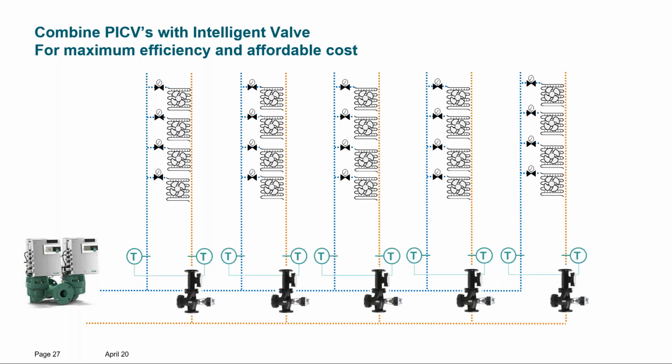And then on the risers and for the big consumers in the air handling units, you can use the intelligent valve solutions. You can add the intelligent valve on the risers. Then you have on the one hand side also the distribution on the riser level under control in regards of flow, but also in regards of power. You can say this riser is allowed to get this amount of power, this riser is allowed to get this amount of power. And if your supply temperature fluctuates a little bit due to high loads at the moment or something like that, you can still guarantee that the power is distributed correctly. On the other hand side, delta T. Delta T not on any coil and any fan coil unit, but delta T in the whole system to provide an optimum operation point for the chiller plant. So that is the main topic.